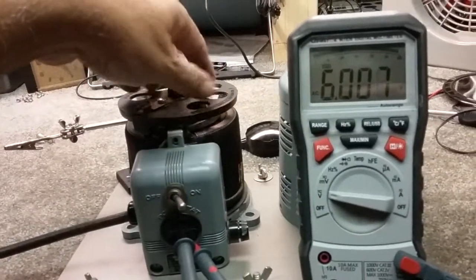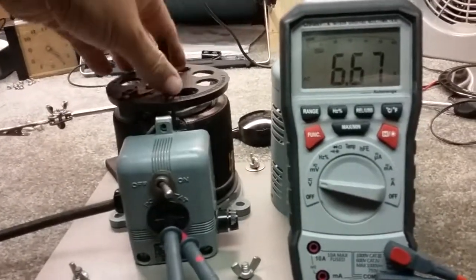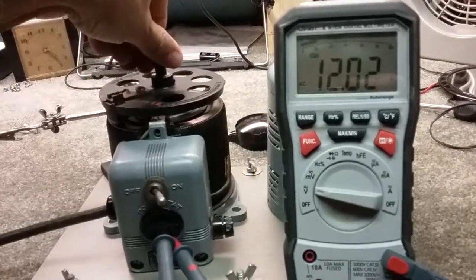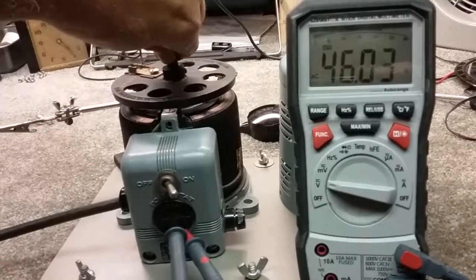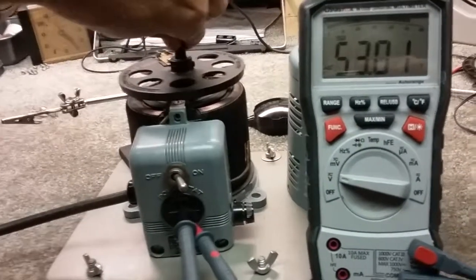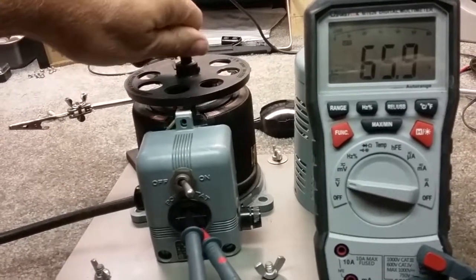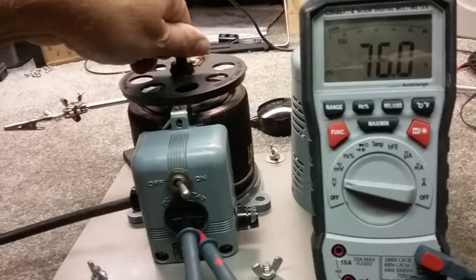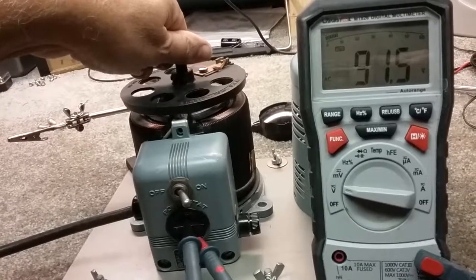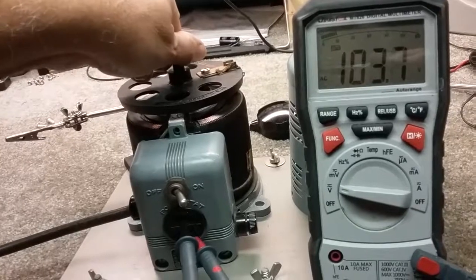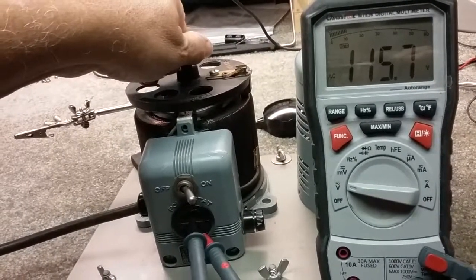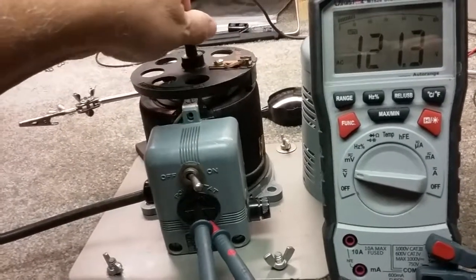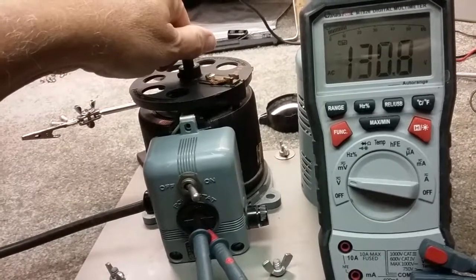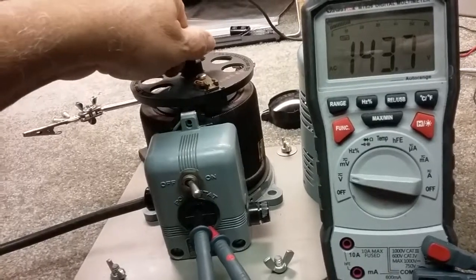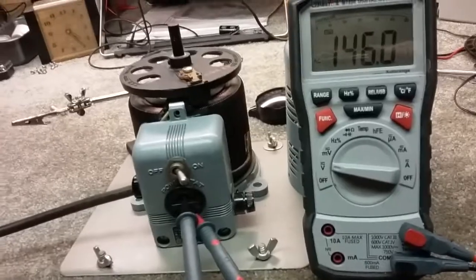This is the contact here for the voltage across the rheostat as it turns around the coil. So we're at 12 volts, and it's nice and snug, as you can see. At 40 there's 52 volts, still climbing fine. 66 volts. 76 volts, 83 volts, and you can see that it's doing fine. Now approaching 115, and you can see I've still got considerable way to go. 121. 130 volts. 143.8, and the max is 146 volts AC.